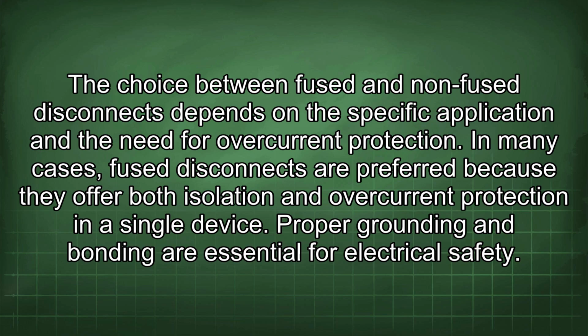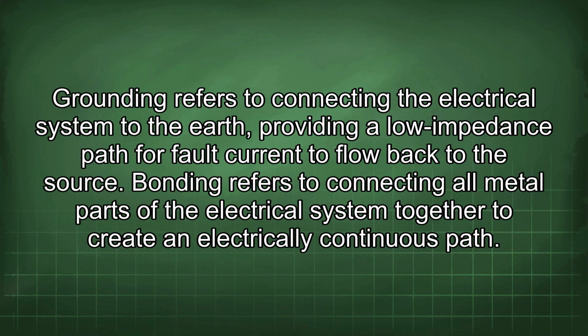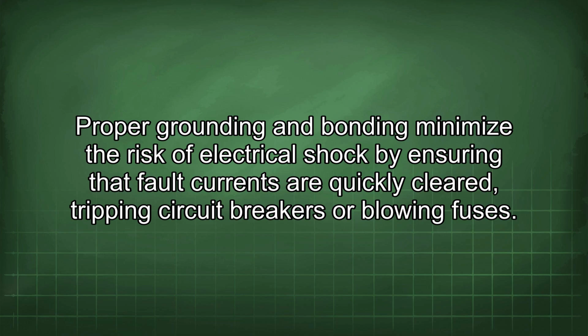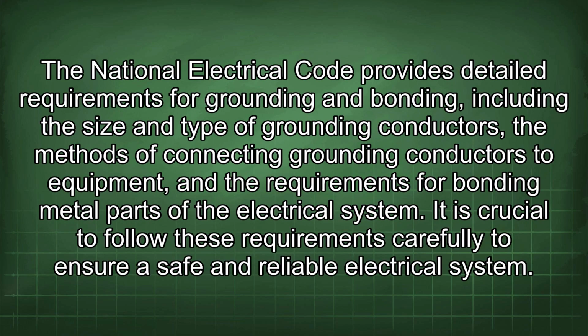Proper grounding and bonding are essential for electrical safety. Grounding refers to connecting the electrical system to the earth, providing a low impedance path for fault current to flow back to the source. Bonding refers to connecting all metal parts of the electrical system together to create an electrically continuous path. Proper grounding and bonding minimize the risk of electrical shock by ensuring that fault currents are quickly cleared, tripping circuit breakers or blowing fuses. The National Electrical Code provides detailed requirements for grounding and bonding, including the size and type of grounding conductors, the methods of connecting grounding conductors to equipment, and the requirements for bonding metal parts of the electrical system. It is crucial to follow these requirements carefully to ensure a safe and reliable electrical system.